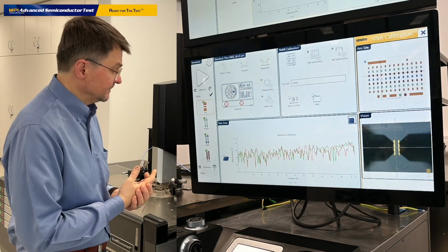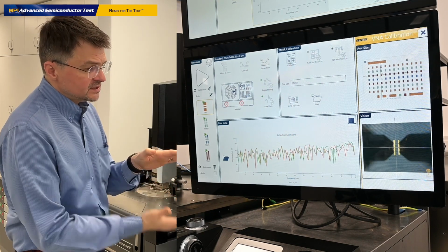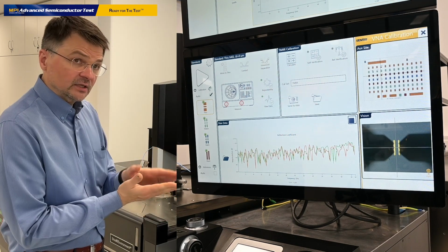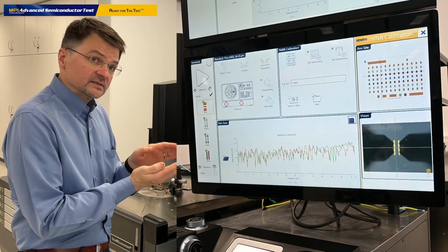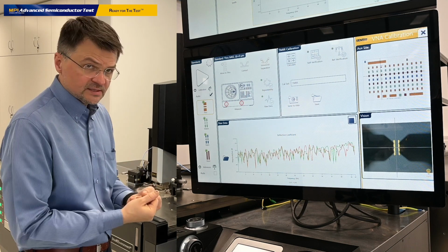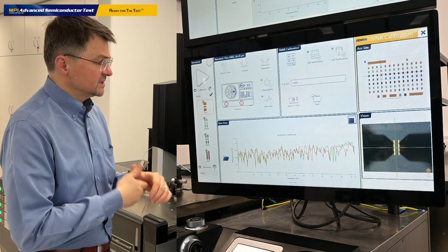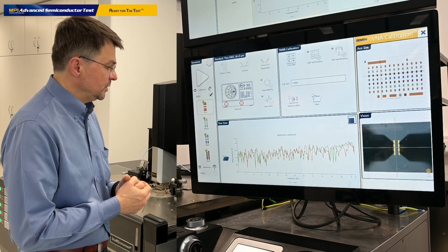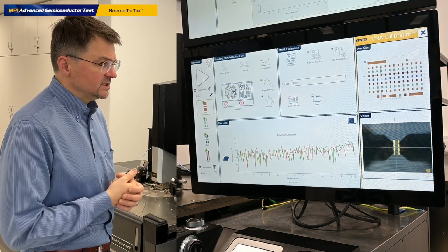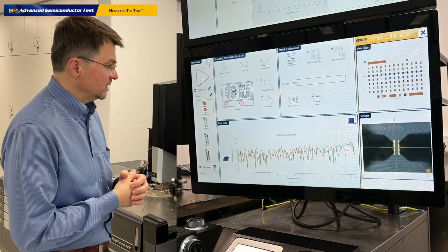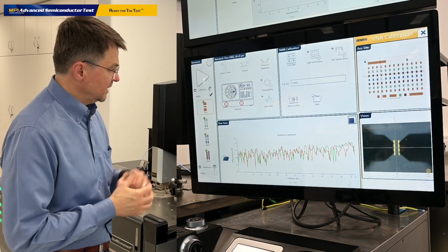So we regularly check for the consistency of the data, with verification algorithms that look into the repeatability of the data, as well as analyze the raw data consistency. The next verification step is the self-verification algorithms, which look into the correct data of reflect elements like open and short during the calibration process. Let us see how this is all executed.